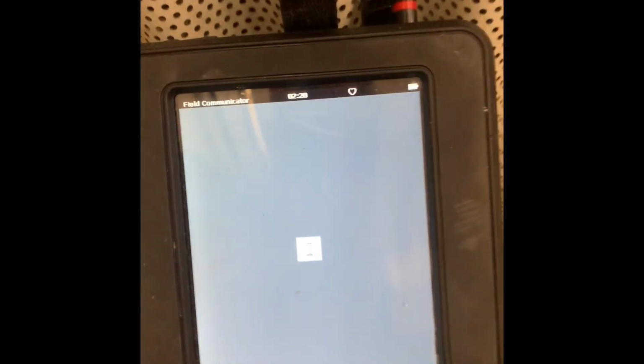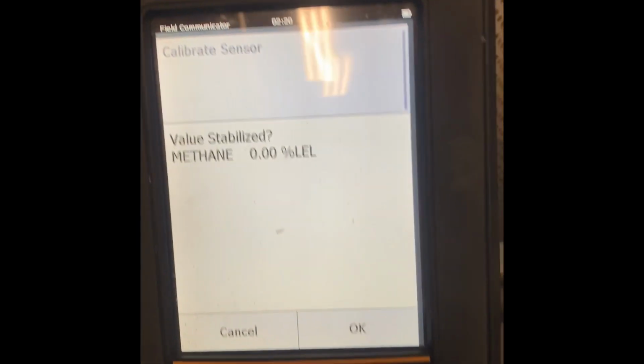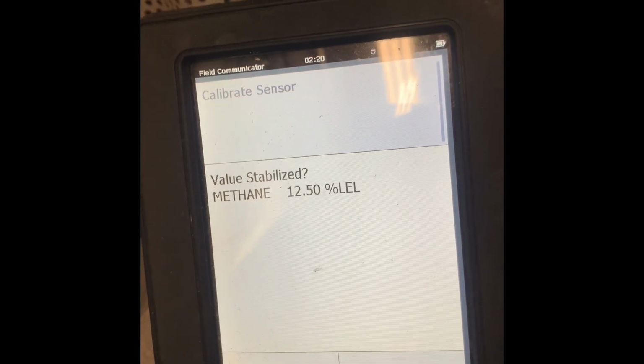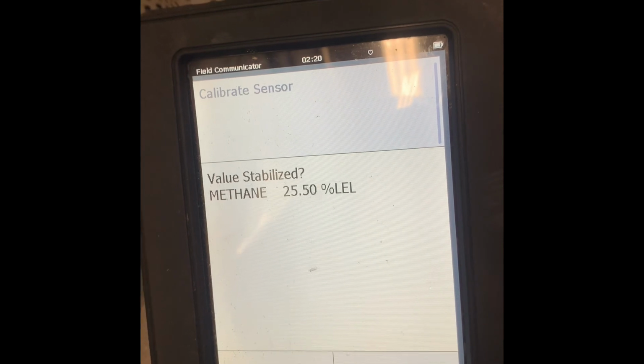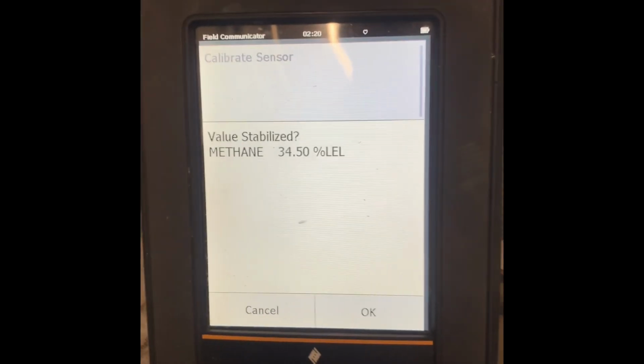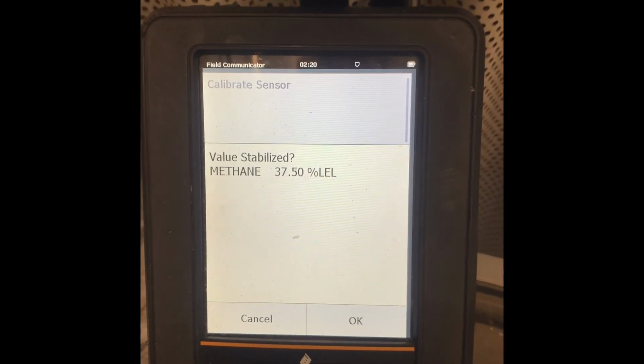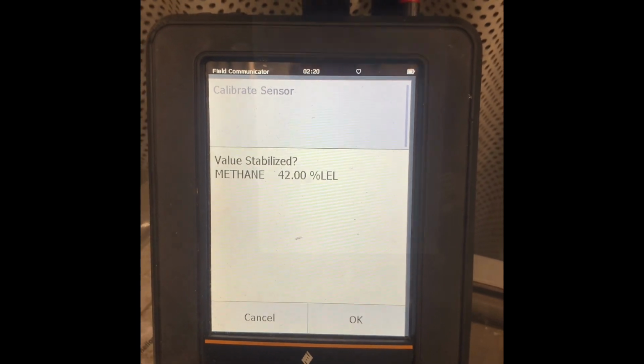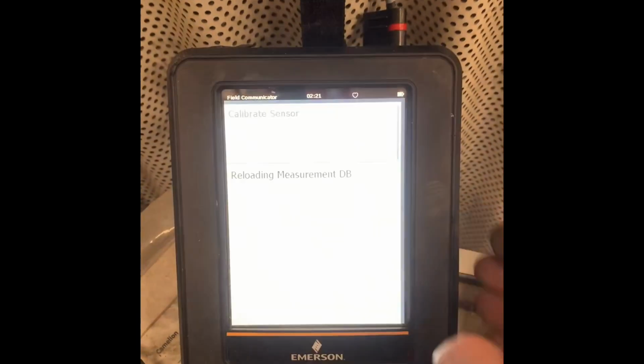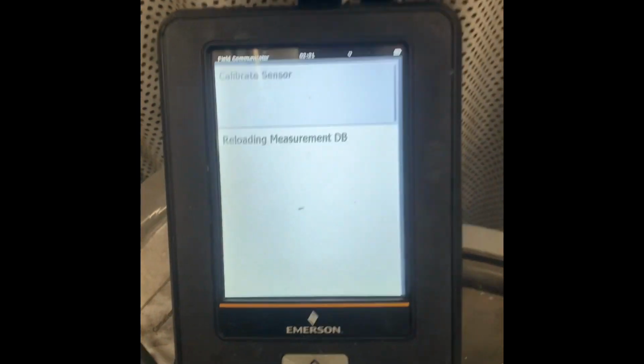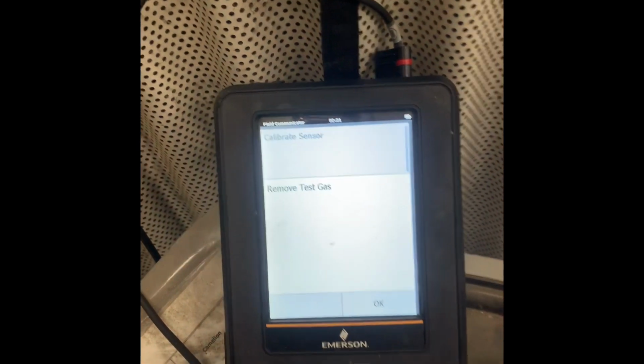So now I hook up my gas tube. I already did. I just turn on that valve, and it's going up to that tube, and now it should start seeing some methane coming through to the detector. It has to go up to the ceiling through the tube. There we go. So as soon as it gets to around 57-ish and then stabilized, I can go ahead and hit yes. And now it's going to recal it at 57.